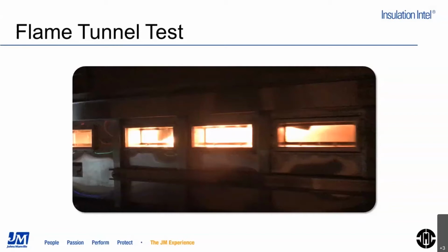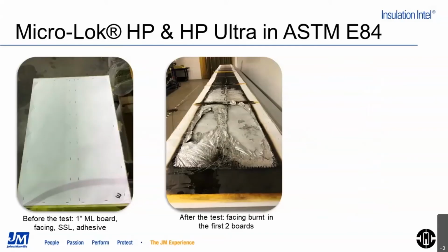So now that we looked at the tunnel, let's have a look at what the insulation looks like after we pull it out. So here we pulled out insulation, we flipped it over, so we're looking at the side that has been facing the flames. And the entire tunnel is laid out on this long table. The closest board to us is the one that was over the burner. This is where we saw all of those flames. And you could see that the facing was damaged on the first 2 boards, but then after that you have charring, and the furthest boards just have a little bit of soot on them and not much else. So yeah, the flames were really quite strong here. You could see there was a little bit of discoloration on the fiberglass as well, which is quite common.